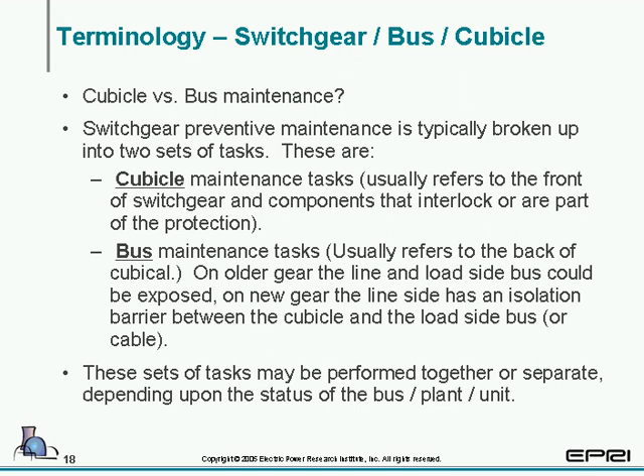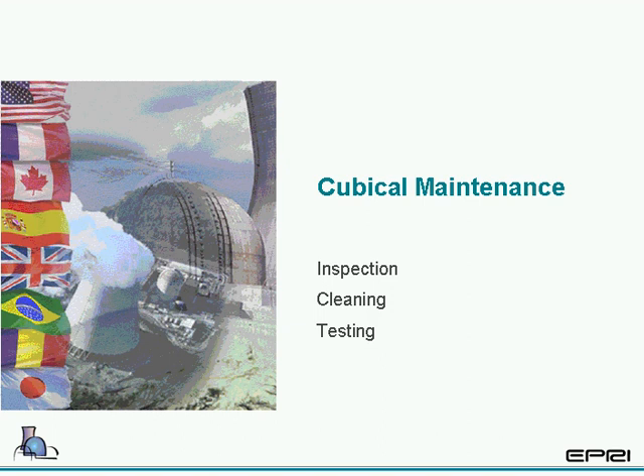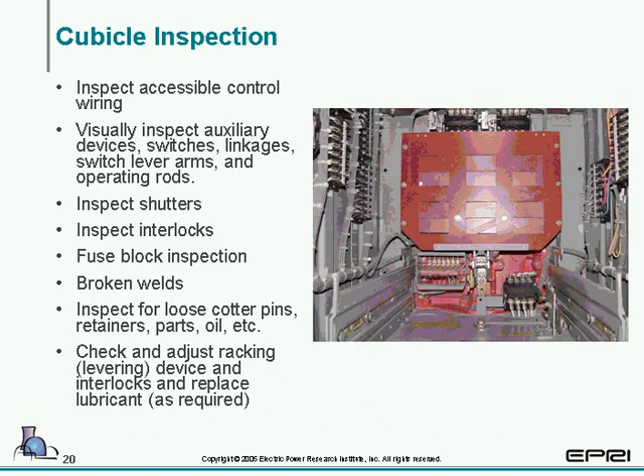Now we're going to take a look at the terminology of switchgear, bus, and cubicle. We spoke about switchgear, and we spoke a little about cubicle and bus. The cubicle is normally found, as stated, in the front part of the switchgear. It controls the interlocks, breakers, and the instrumentation. The bus is usually found in the back compartment or the back door. When you open it up, you may or may not see all of the bus. The very first thing we're going to take a look at is we have bus and cubicle, and we're going to take a look at cubicle first and bus in a minute.